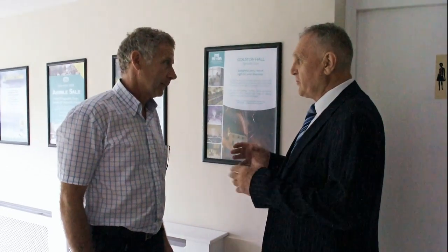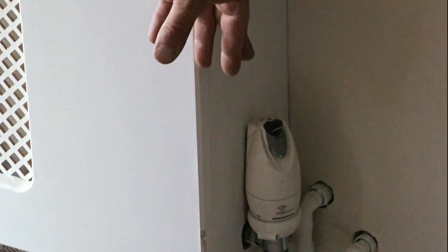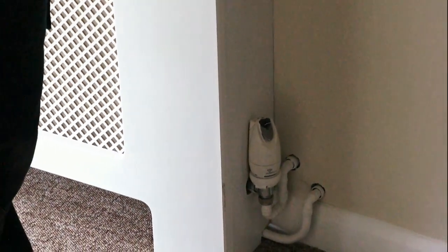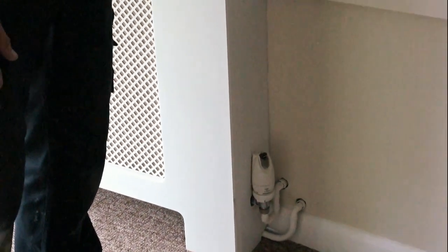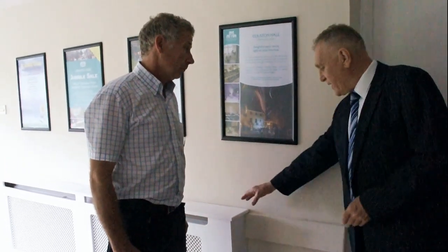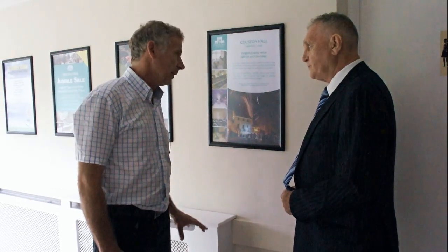And this is another room you're zoning using the wireless TRVs. So that's this one here — the wireless TRV picking up off the main system on the ZigBee network, and then that automatically controls the radiator valve. So on the ZigBee network, that's talking to this valve and giving it the temperature it needs at that particular point in time. And are all the rest of the radiators covered like this? Some have covers, some haven't. We've got a mixture in the building, and we've got quite a few temperature and humidity sensors on the walls within the rooms that are controlling those.